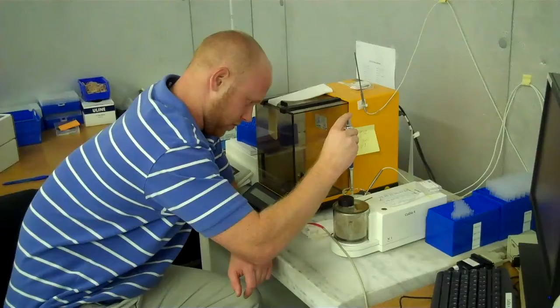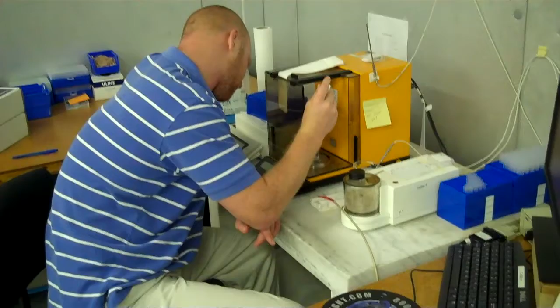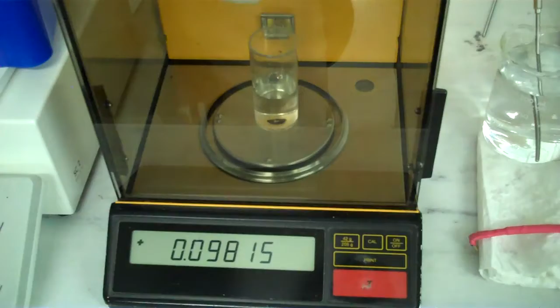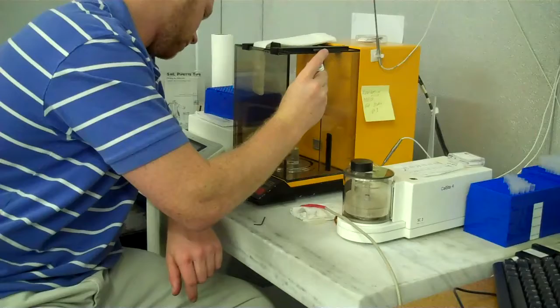The technician aspirates and dispenses 4 shots of water into a flask on a 5-place scale. The mass of each shot is recorded by our calibration software. This software then uses these values to calculate the accuracy and precision of the pipette. If the pipette is found to dispense either too much or too little liquid, it must be calibrated so that it dispenses within the manufacturer's specs.